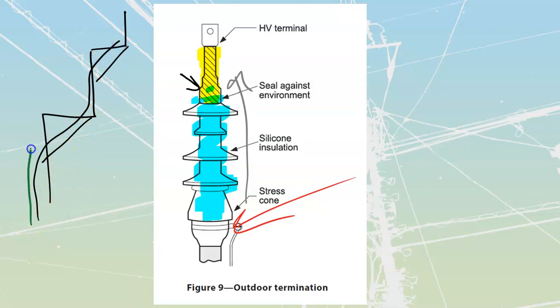If I placed something over top of something that wasn't penciled and shrunk it like that, we'd have an area over here where we get trapped air, and that trapped air is going to break down. It forms corona inside of here, and that corona is a free radical. It's going to eat through a lot of your insulation and cause this thing to fail early.